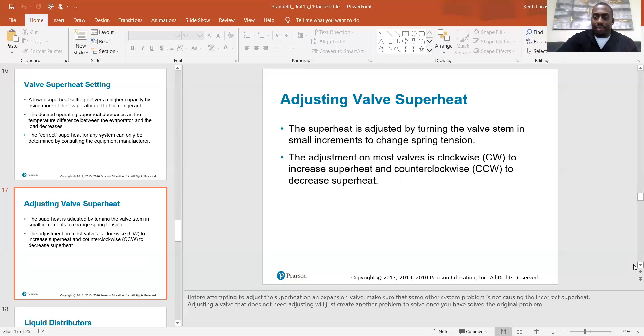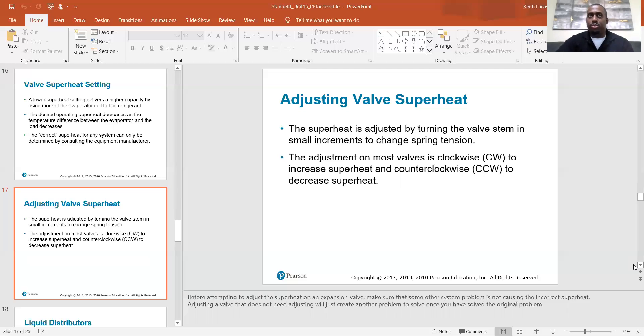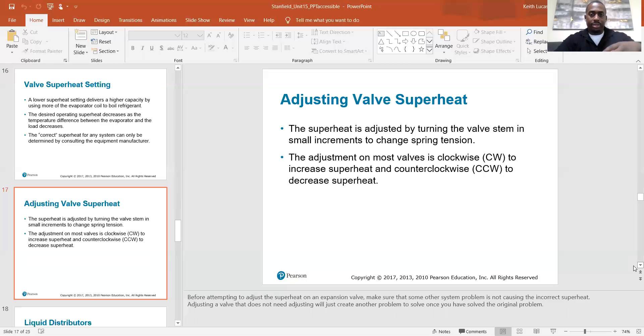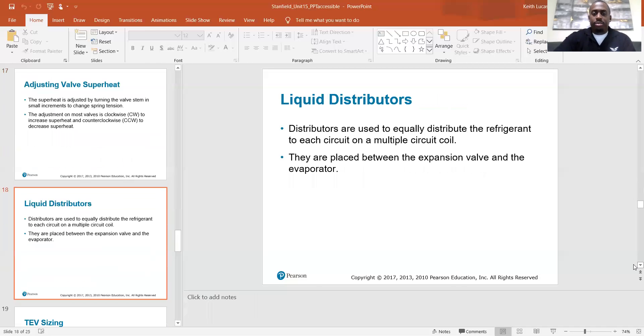I've had that happen — I made an adjustment, then found the real problem, corrected it, and went back to check everything, only to find things were still off because of my earlier adjustment. I had to go back and re-adjust the TXV back to where it was in the first place. So check the simple stuff before you make any determinations.